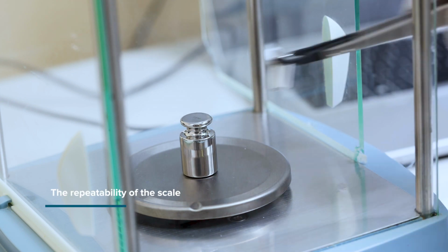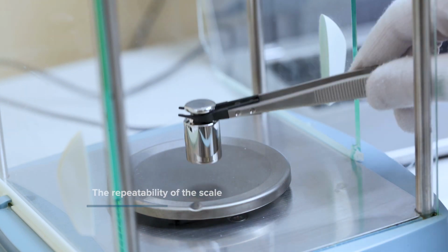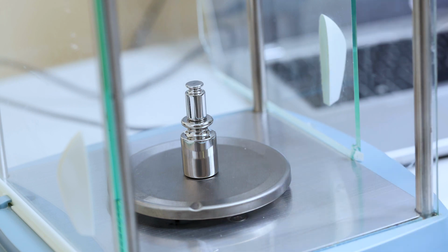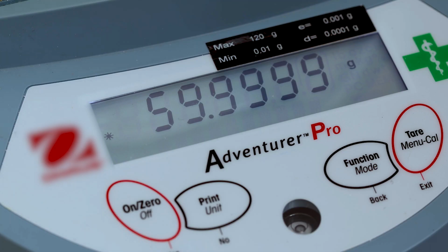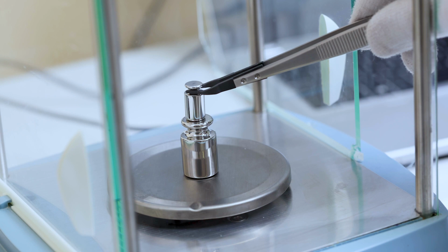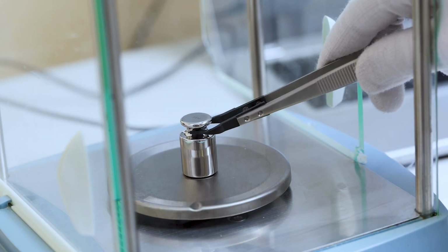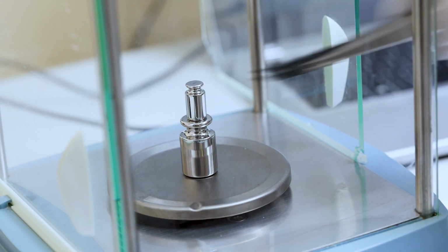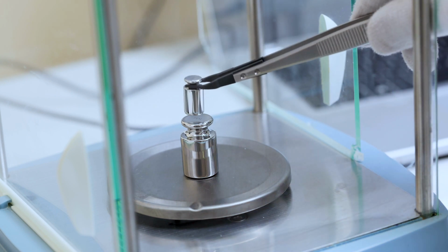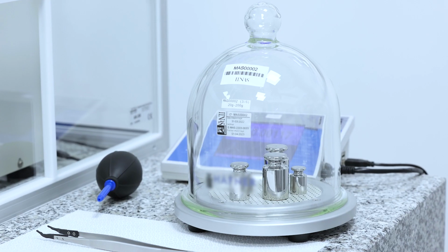The repeatability of the scale must also be taken into account. For this purpose, the operator uses a weight with a value of approximately 1/2 of the maximum range. Then he carries out at least 5 successive measurements while taking care to note the value without the weight and with the weight. This is more commonly known as the repeatability test.